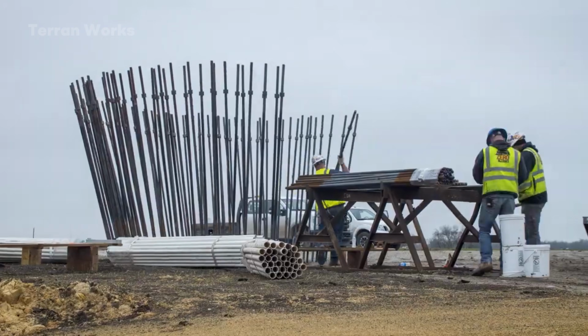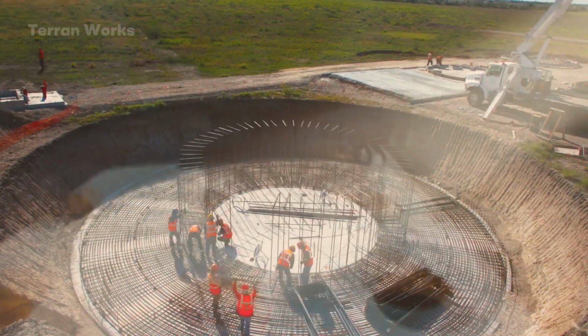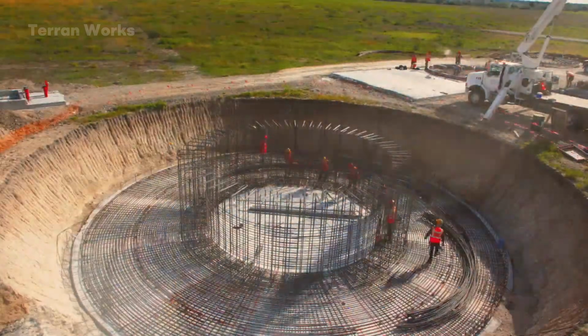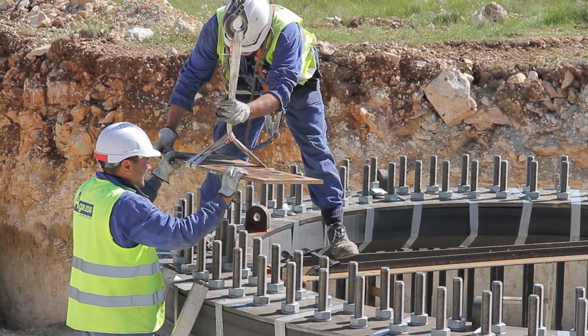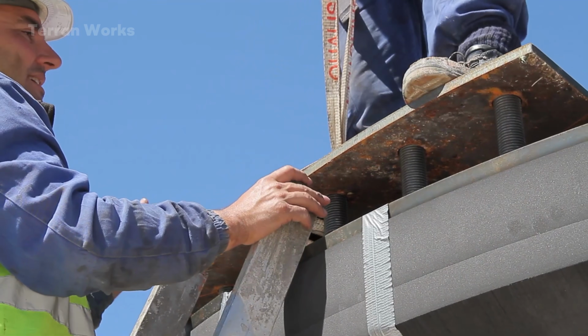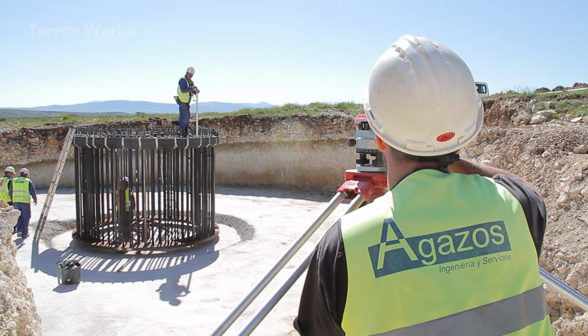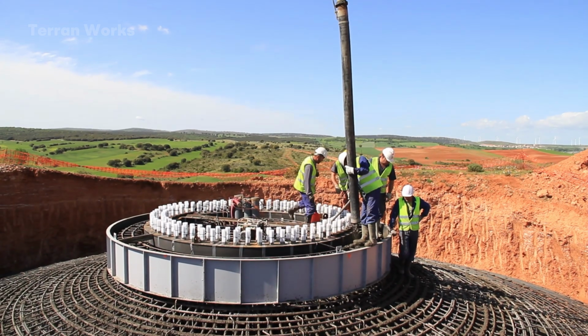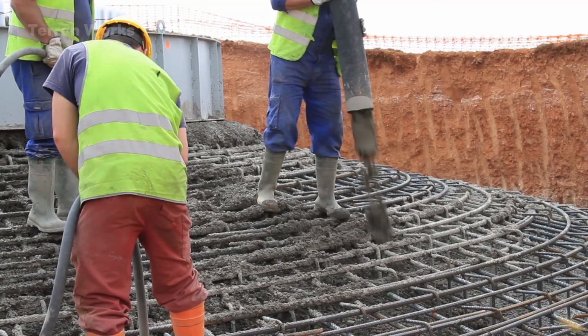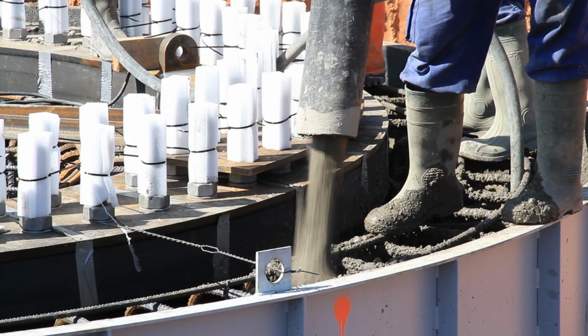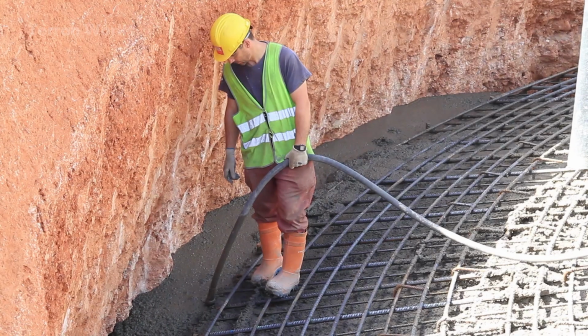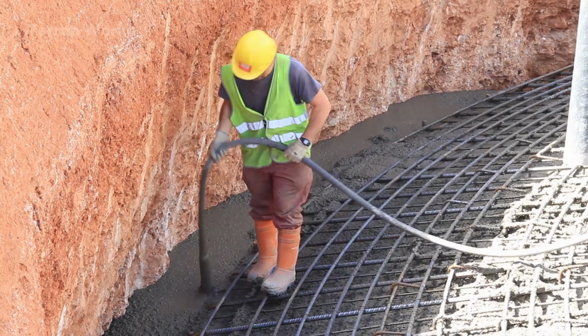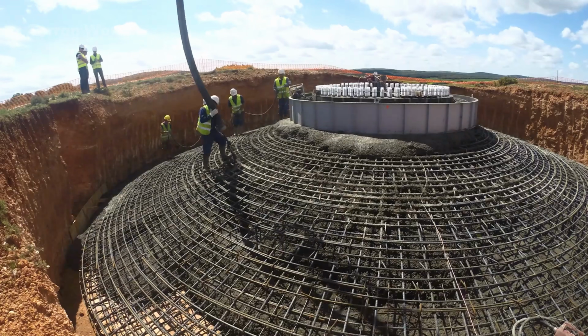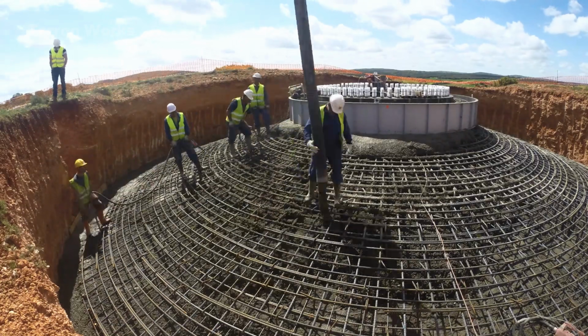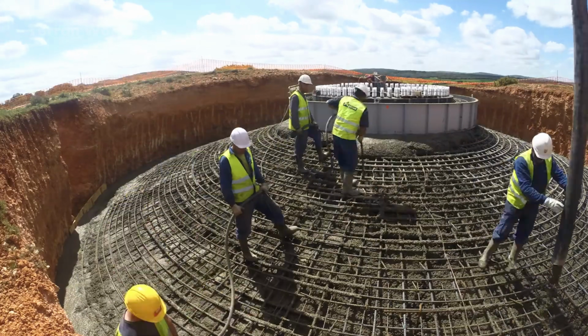Next, a reinforcing steel cage weighing around 20 to 60 tons is installed inside the foundation pit. At the center, a massive anchor bolt system is positioned with precision so it can later connect to the tower body. After that, concrete is poured continuously to form one seamless block. Each modern onshore turbine foundation may require 300 to 700 cubic meters of concrete, equivalent to 40 to 90 concrete mixer trucks with an 8 cubic meter capacity.